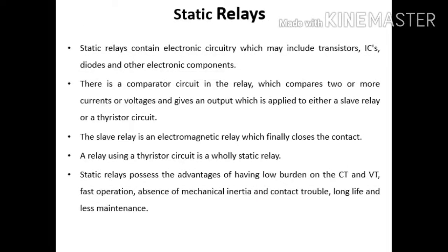Static relays. These relays contain electronic circuitry which may include transistors, ICs, diodes and other electronic components. So these relays will have a comparator circuit which compares two or more currents or voltages and gives the output which is applied to either a slave relay or a thyristor circuit.